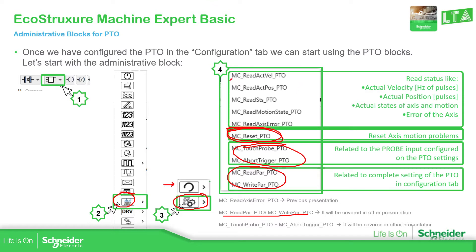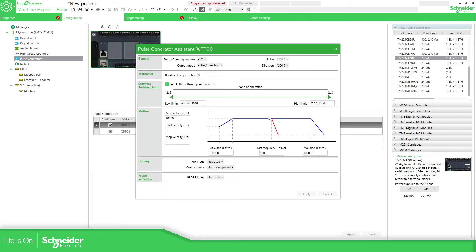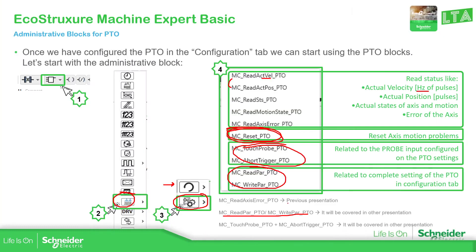The first two elements allow us to see the velocity and the position. Something important here: the velocity is in Hertz, which is related to how we have configured it in our software. There is no RPM or anything like that — it's just the frequency of the pulses that we are sending. This is what we receive on the function block as actual velocity. For the position, it is the number of pulses that we are sending from the PLC to the drive.